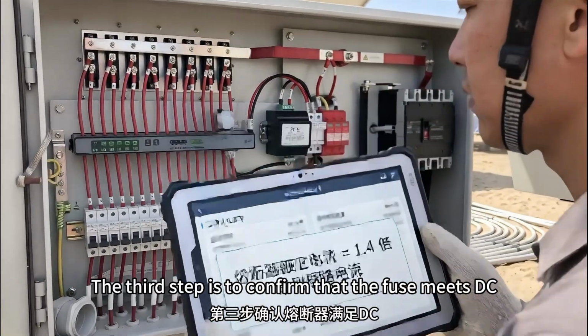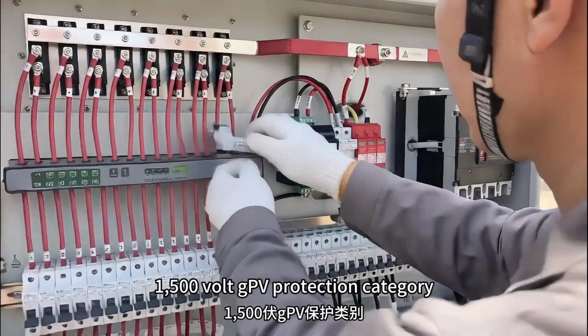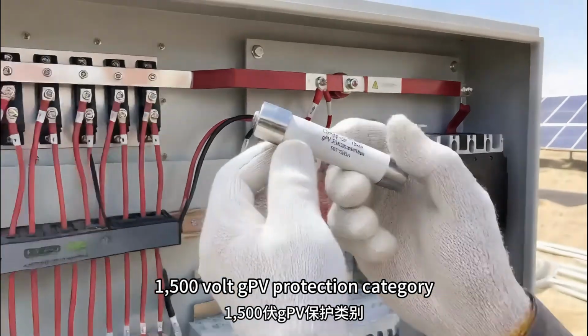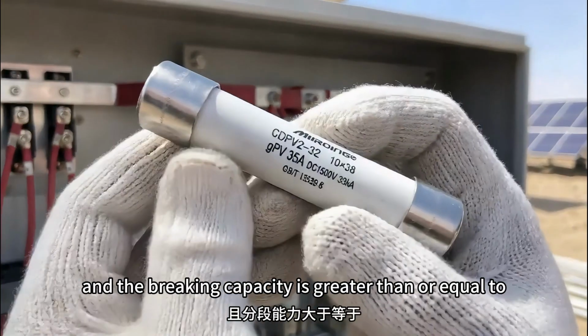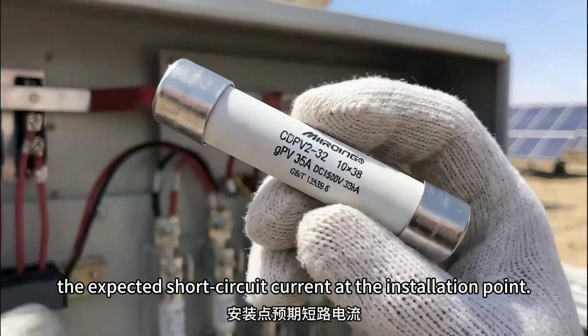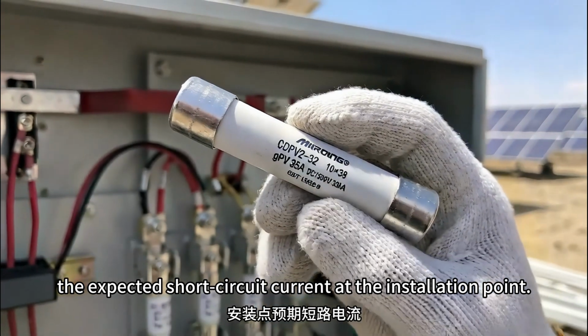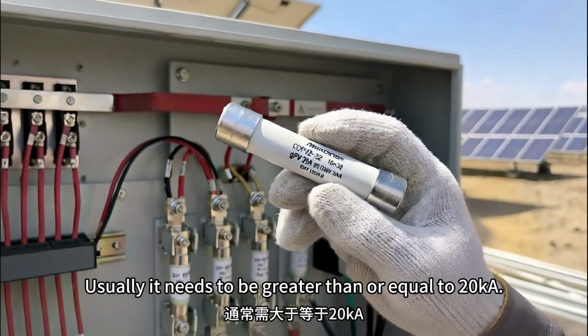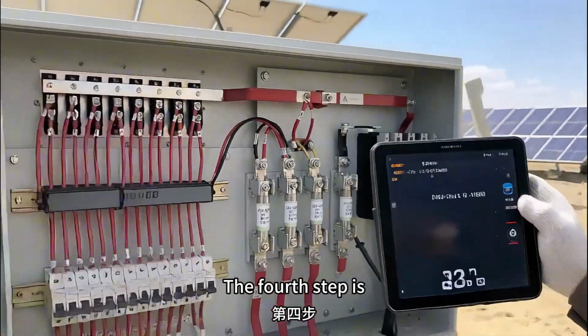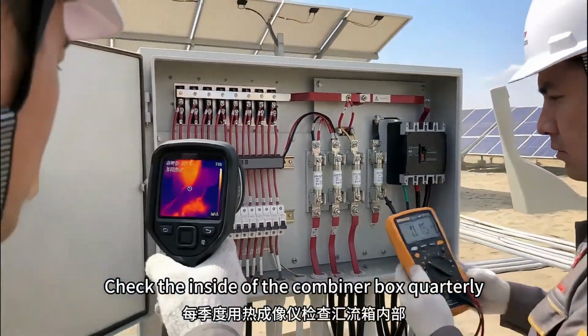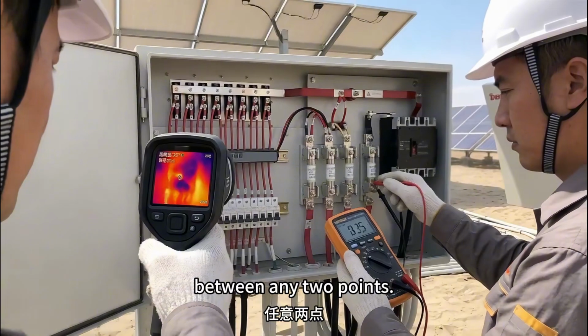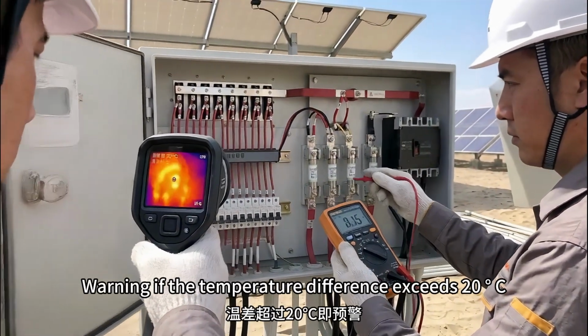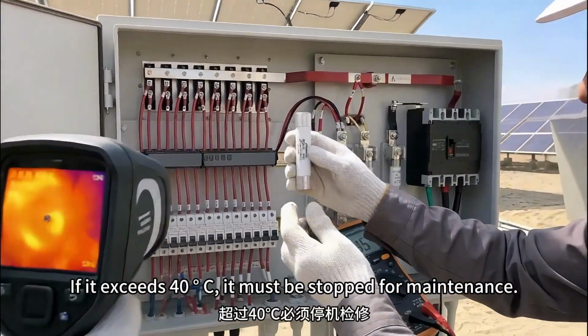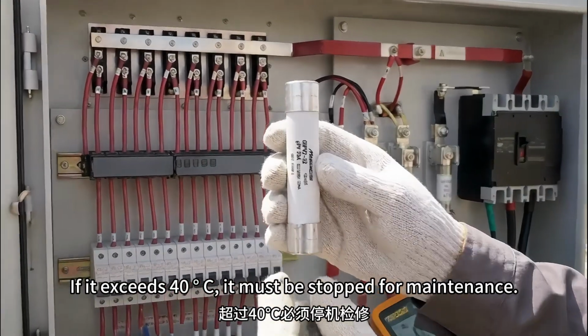The third step is to confirm that the fuse meets the DC 1500 volt GPV protection category and that the breaking capacity is greater than or equal to the expected short circuit current at the installation point. Usually it needs to be greater than or equal to 20 kA. The fourth step is to check the inside of the combiner box quarterly between any 2 points. Warning if the temperature difference exceeds 20 C. If it exceeds 40 C, it must be stopped for maintenance.